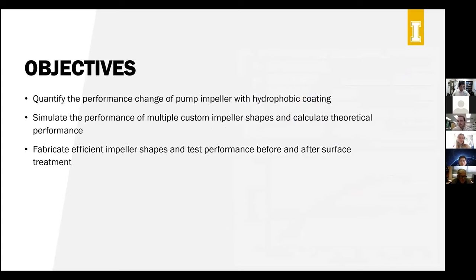Yeah, so the main objective for this research was to quantify the pump performance change with an impeller redesign and hydrophobic coating. In order to do this, we felt the need to simulate performance of multiple custom impellers to deal with the angle change of those vanes and change the shape of the impeller, and then calculate those theoretical performances for those different designs, and then fabricate efficient impeller shapes and test the actual performance in an actual pump loop with various surface treatments to see how hydrophobic coating and impeller redesign affect efficiency.